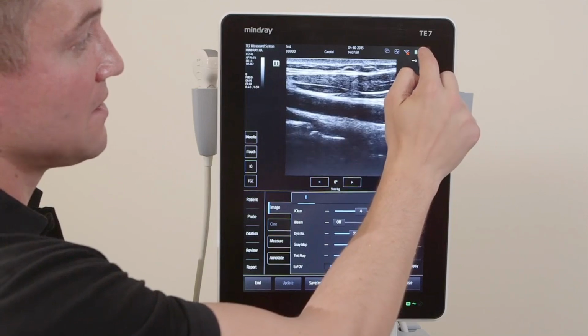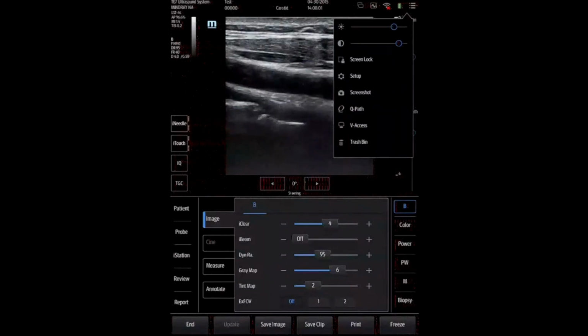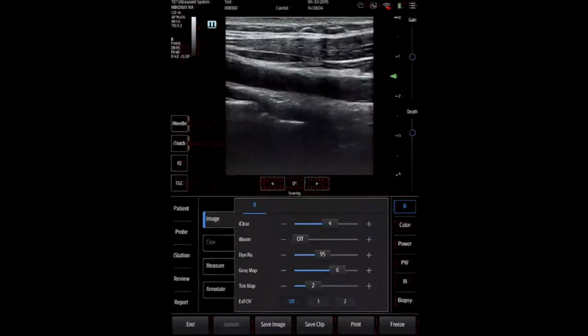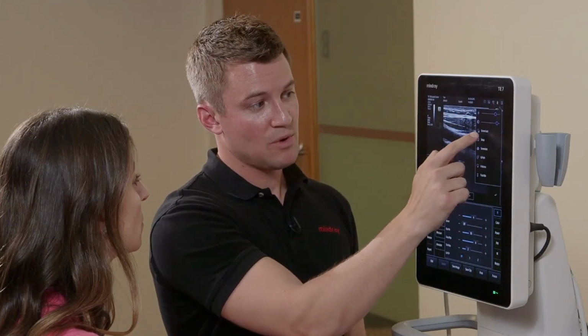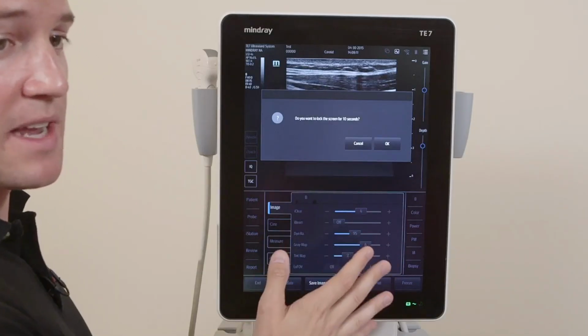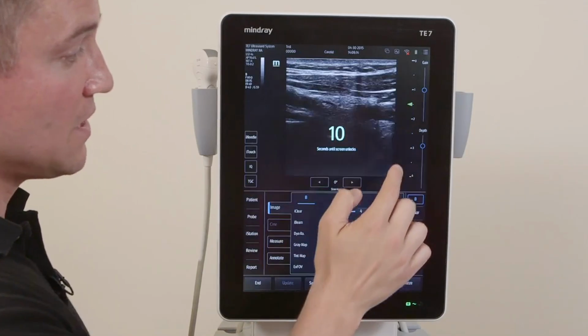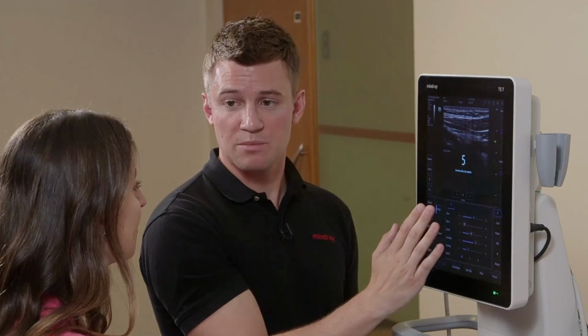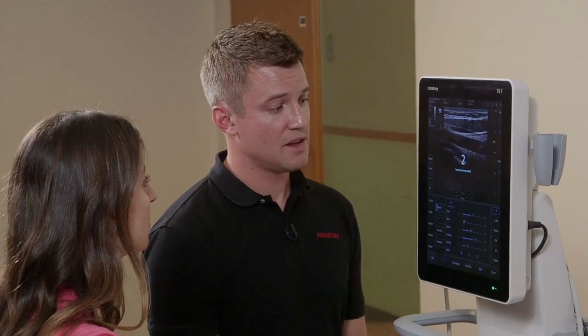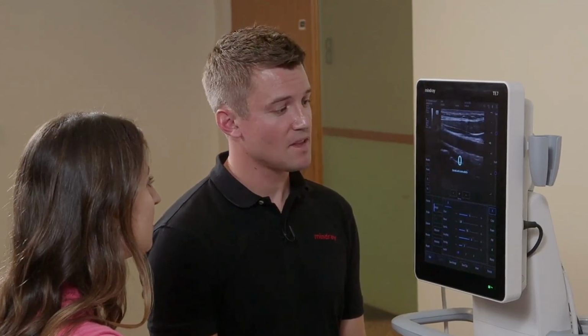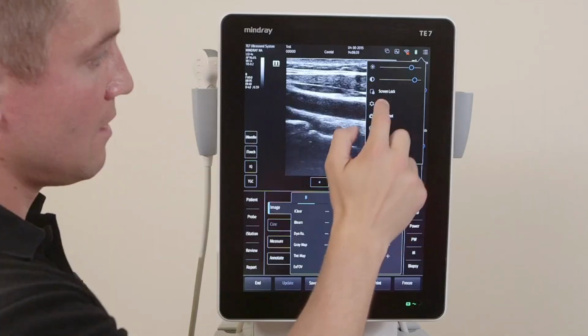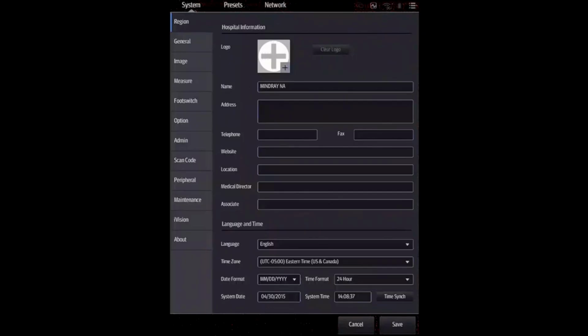As well as our setup menu. Here we're able to change our screen brightness and contrast, as well as do a few other things in terms of admin control. One of the things I want to point out right now is the screen lock. We need to be able to clean the slate. And so this has an auto screen lock for 10 seconds. So now I can take my cleansing cloth and wipe down my screen without worrying to change the parameters and things of that nature. And after 10 seconds it'll unlock and you can be on your way. That's nice. Other things that you can look at there in the setup menu is the ability to input your facility name as well as your address amongst the time and date and whichever region you're in, and then being able to change some of the other parameters that we'll discuss as we go through the rest of the tour of the TE7.